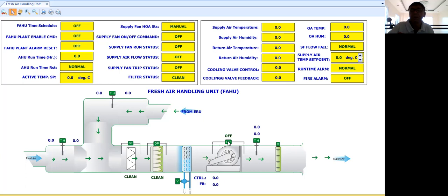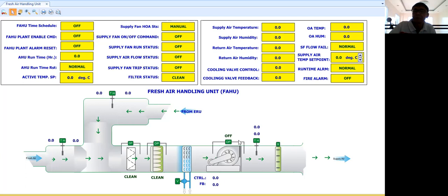Make sure to set the setpoint. In my experience, the differential pressure range for this switch is around 200 Pascal, so you can set it to 80 to 100 Pascal. When the differential pressure across the fan reaches the setpoint — say 80 Pascal — a normally open contact in the differential pressure switch will close, and you use this for your airflow status signal.